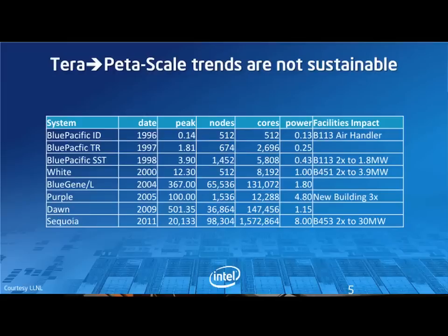In order to upgrade that facility, we had to double the power and airflow into that at a cost of about $500,000. So the next system came in, was a little bit more than that. Started with 4-way processors, 4-core processors, a much larger system, and then that became the nucleus of the 3rd generation system. And notice now the power starts to climb, and we ended up, as I mentioned, doubling the power in that building. And then we figured out that the next system wouldn't fit into that building, ASCI White.